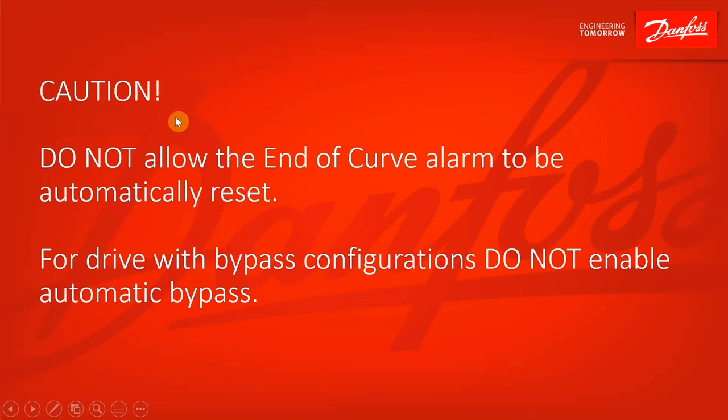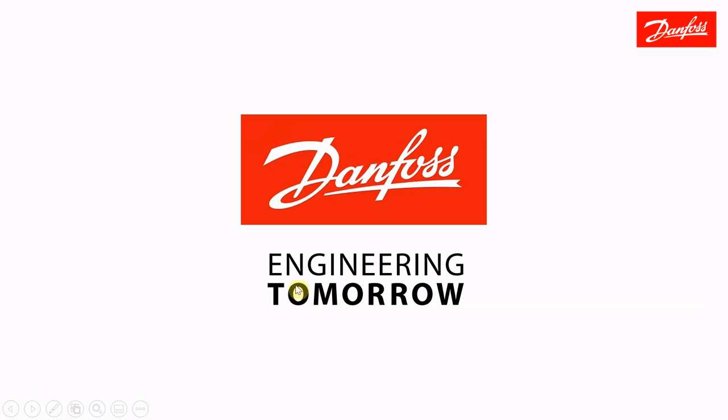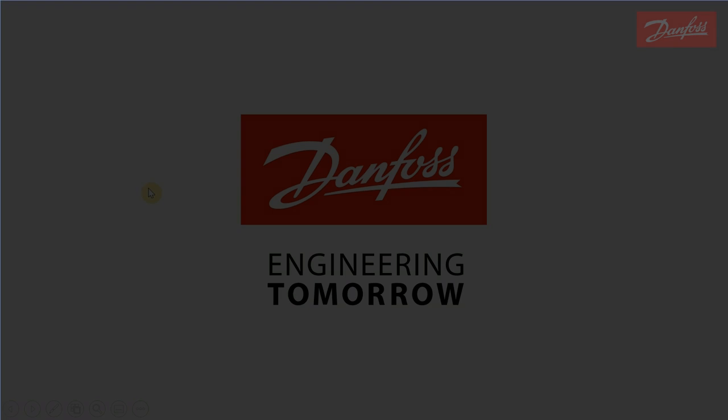So again, remember, you do not want to allow that end of curve alarm to be automatically reset, and you do that either by checking manual reset and alarm, or by turning off your auto reset. Make sure you do not have automatic bypass enabled. So that's the end of curve feature. Thank you for listening. Thank you for viewing.